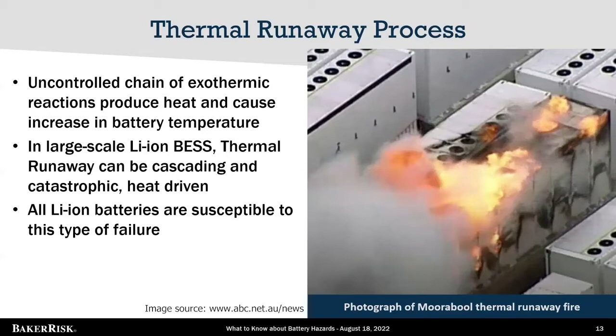In large scale BESSs, these thermal runaway events can cascade from cell to cell, throughout an entire module to the next module, through the whole rack, and consume the entire BESS enclosure. Here's a photograph from an event in Moorabool, Australia, where it was able to cascade over to an adjacent BESS enclosure. Basically all lithium ion batteries are susceptible to this type of failure.